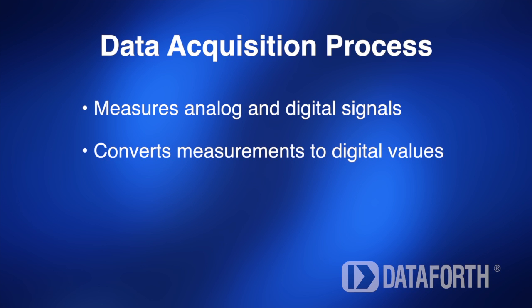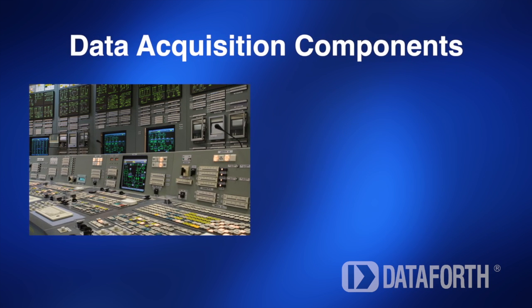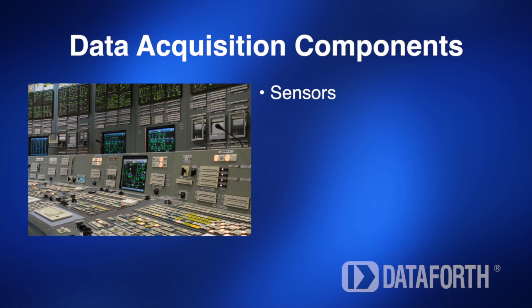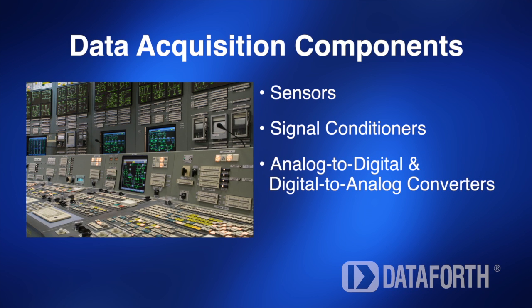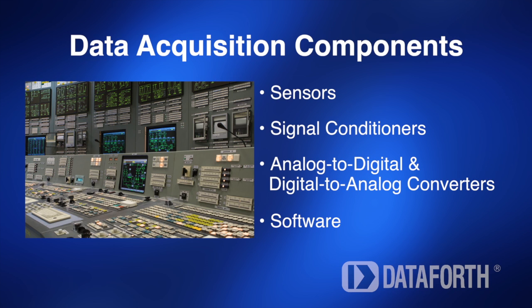Then digitizing the measurements for manipulation by a control system. The components of a data acquisition system include sensors to provide the analog input signals, signal conditioners to filter, amplify, isolate, and linearize input and output signals, analog-to-digital and digital-to-analog converters, and software, which allows data acquisition hardware to work with a host computer and control applications.